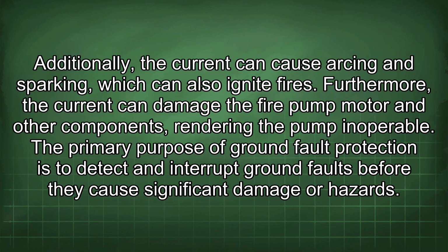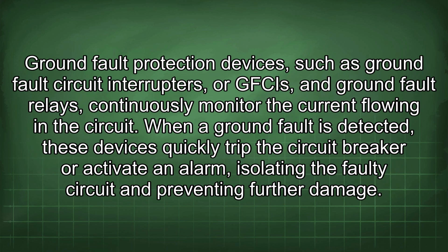The primary purpose of ground fault protection is to detect and interrupt ground faults before they cause significant damage or hazards. Ground fault protection devices, such as ground fault circuit interrupters, or GFCIs, and ground fault relays continuously monitor the current flowing in the circuit. When a ground fault is detected, these devices quickly trip the circuit breaker or activate an alarm, isolating the faulty circuit and preventing further damage.